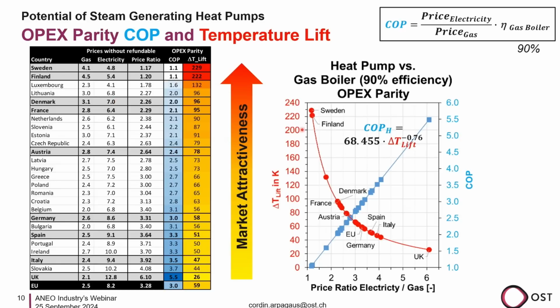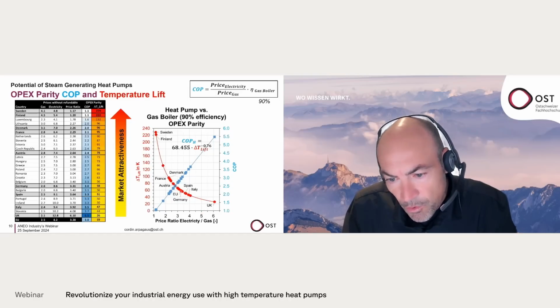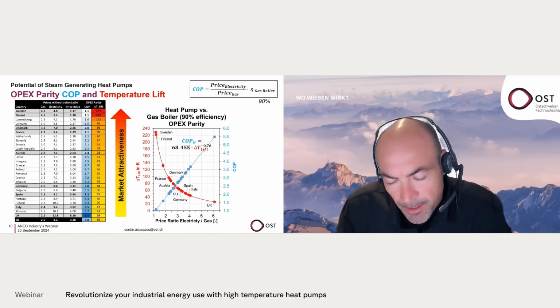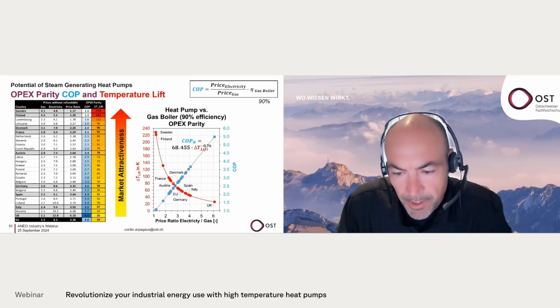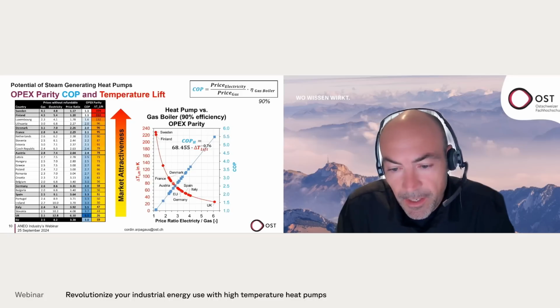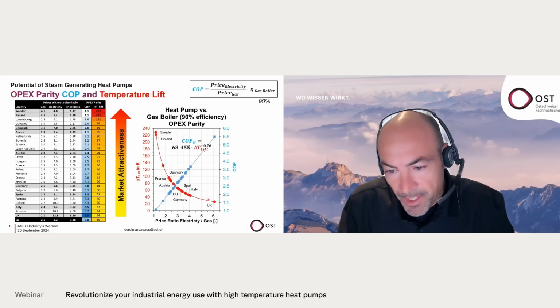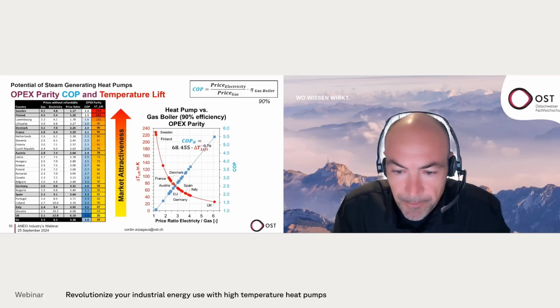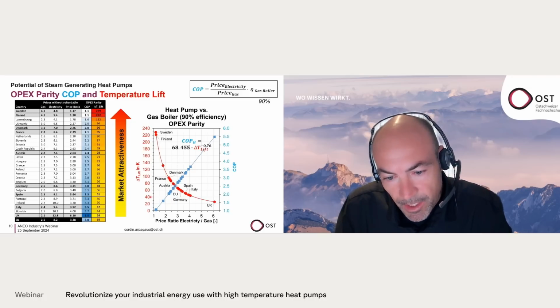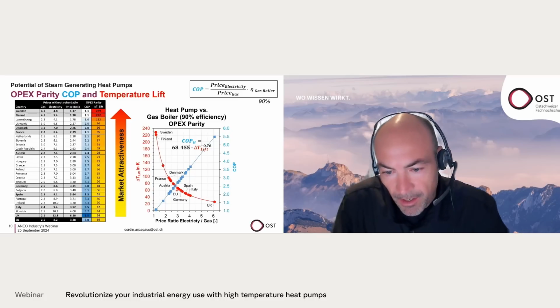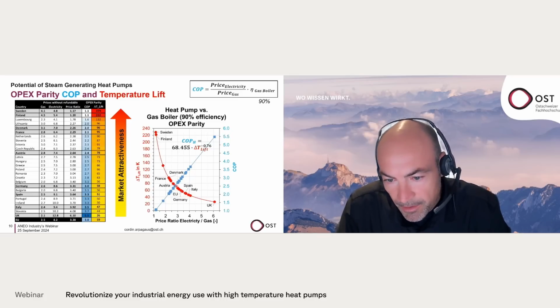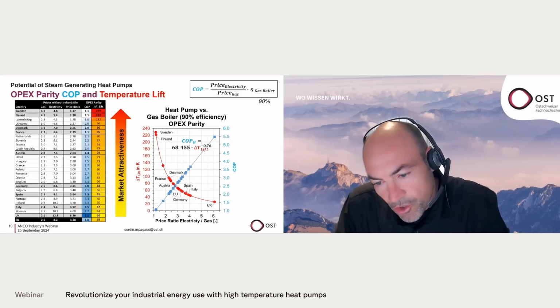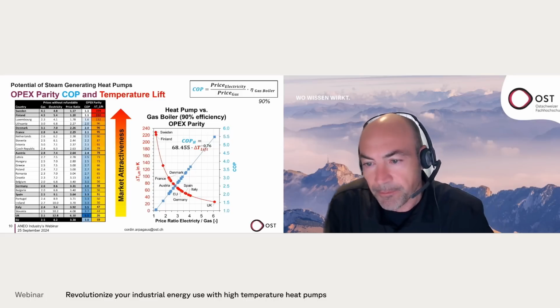We can do a comparison of the OPEX, operating cost parity, between an electrically driven heat pump and a gas boiler. Here we see that we move along such a curve: the temperature ratio determines the COP, and the price ratio determines the economic temperature lift. We see that temperature lifts between roughly 40 to 60 degrees achieve a COP of 2 to 3, which is an average in Europe. So the goal should be to push this towards the left.